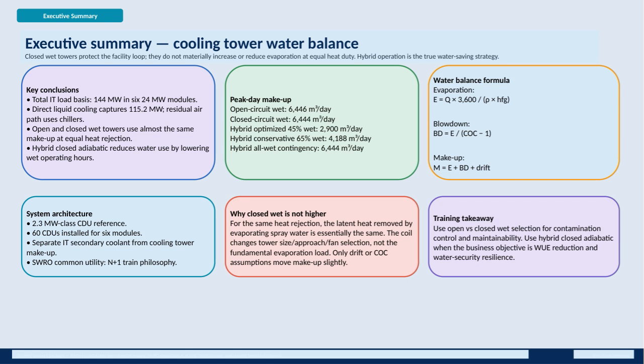In terms of system architecture, the reference coolant distribution units, or CDUs, are about 2.3 megawatts each. 60 of these units are installed across the 6 modules. Importantly, the IT secondary coolant is kept separate from the cooling tower's makeup water, and the seawater reverse osmosis system follows an N+1 redundancy approach to ensure reliability.